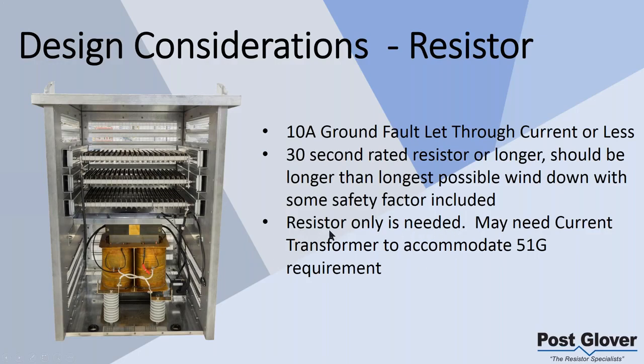Only the resistor is needed. I see a lot of people looking to try to use an HRG system, like a pulsar system, with their hybrid resistance ground system. You don't actually need all that stuff. Really, because of all the relaying you have, you really just need the resistor. You may need a current transformer to accommodate the 51G inside the resistor itself, but more likely in this scenario, especially with the scenario that I showed you before, you probably would have that at the differential. You probably use that in coincidence with the differential relay, which you already need CTs for.